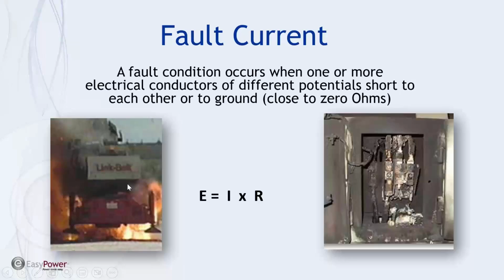The picture on the left shows a crane making contact with a power line. There's an incredible amount of energy in the fault current that occurs when this happens. This is a ground fault, but you can see it took the crane off the ground by about a foot. And then this is the very beginning of the bang, right when it made contact. I've got the whole series of pictures. Of course, the whole thing becomes engulfed in a big ball of fire, but this is just showing you what power can do. The picture on the right is what over-dutied equipment would look like. So this is equipment that is not rated for the fault current, and so it fails, and it heats up, and of course then you could have injuries and outage time and a bunch of different things that could happen.